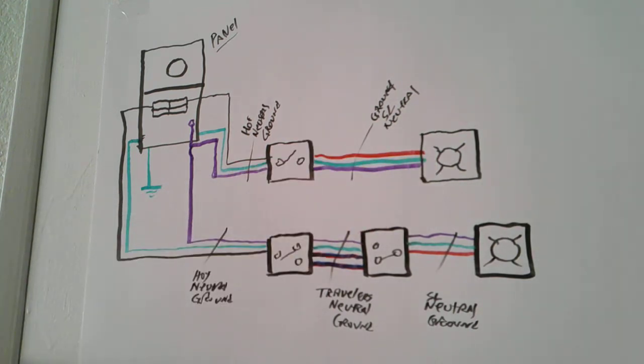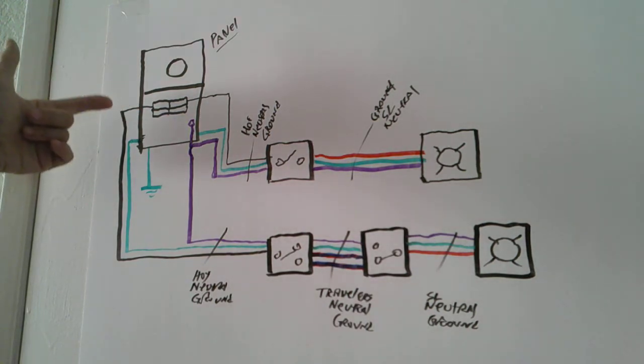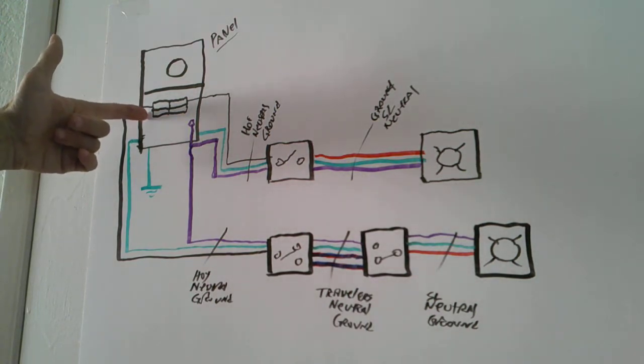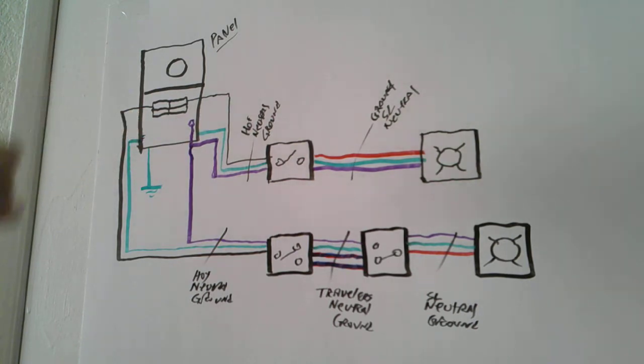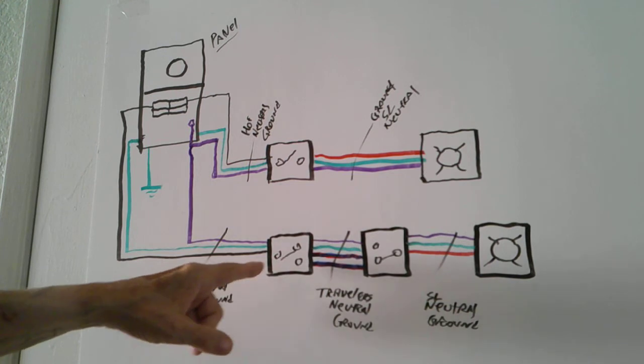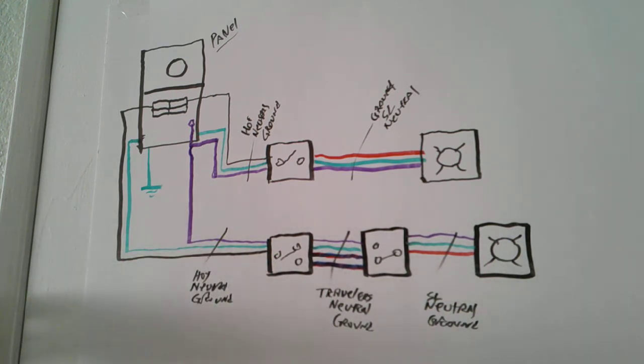Now, let's take a look at three-way switches just for a minute, because oftentimes three-way switches are very confusing. So again, we're coming off of a circuit breaker. You want to check to make sure you have power at the circuit breaker to the neutral or to the ground. Then you want to check this group of wires by going to the first three-way switch and see if you have power there. Now, in that three-way switch, you will have a neutral, you will have a ground, and you should have a hot wire.